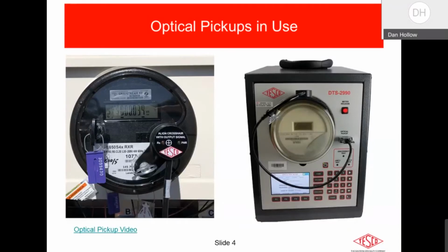So on the left, we have an optical pickup on a meter in the field. This meter over on the left is being tested in the field with a site analyzer. And that type of device is testing the meter for accuracy under customer load. It can also be tested under phantom load. So if this is a dead service, such as an irrigation type service, a pivot, or some sort of irrigation pump, those are deactivated typically 6 months out of the year. So in those kinds of cases, you may have to have battery powered test equipment, since a lot of times they even disconnect the line side voltage. So the meter itself may be dead or the meter may be energized, but not seeing any current outputs from the CTs. In those cases, you have to use a phantom load.